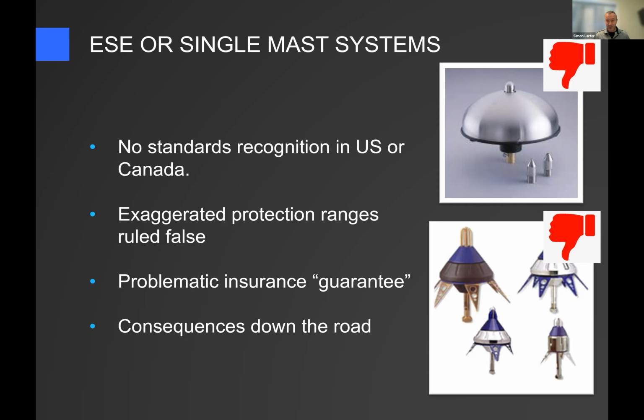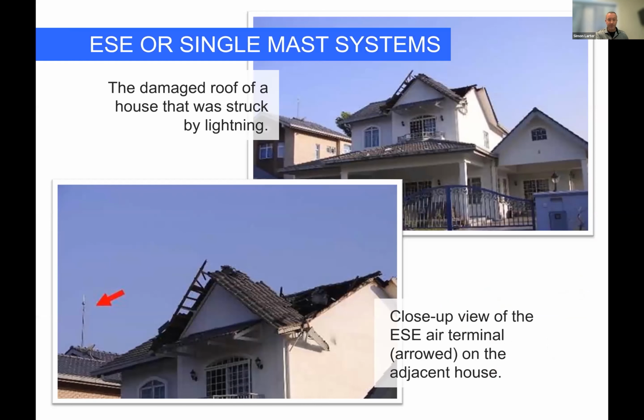I've seen these things fail multiple times myself with my own eyes. I've been on buildings where they got struck when they had one of these things and they weren't supposed to be struck. That thing was supposed to capture the lightning strike, but the building itself took the hit instead, because they didn't have these within 600 millimeters of the outside corners and all that stuff. They're usually on a single tall mast that sticks up and it's supposed to protect a big wide area. It just does not. That's the problem.